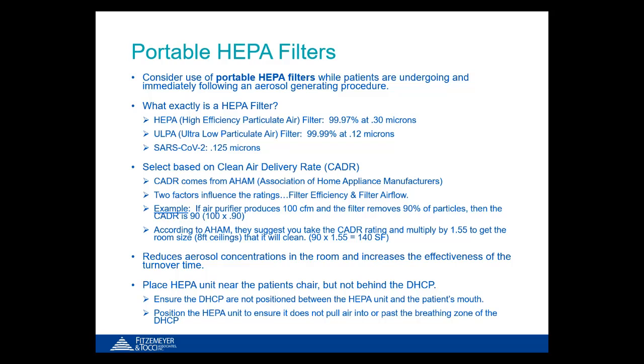The CDC says to select these HEPA filters based on clean air delivery rate, which is a little bit of a different term than engineers are used to using. We've historically used air changes in these rooms, but they want us to base everything on clean air delivery rate. There are two factors that influence the ratings: filter efficiency and filter airflow.